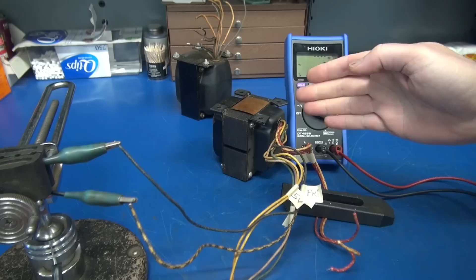Number one, when you get ready to measure this, do not connect from red to red — we don't want to throw the entire potential of the transformer into the meter. Instead, go from red to the red-yellow center tap. So let's say we saw 200 volts AC — we'd know this is a 400 volt center tap high voltage winding.